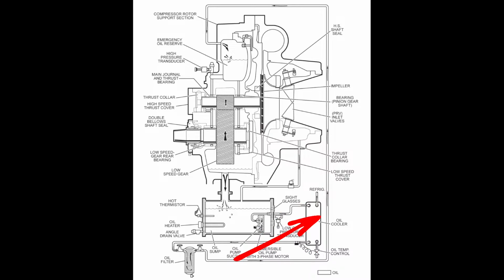So, just things to think about in how you're going to troubleshoot the refrigerant circuit on this. Now, in the case that all of this checks out, temp sensor's good, oil level, heater, and the cooler all seem to be functioning, then we get into our worst case scenario: there may be just something mechanically wrong. Keep in mind, our oil is what is cooling all of these components up here. So this is our pinion and bull gear. This is how we're transitioning from a low speed to a high speed shaft. All of this is cooled by the oil.